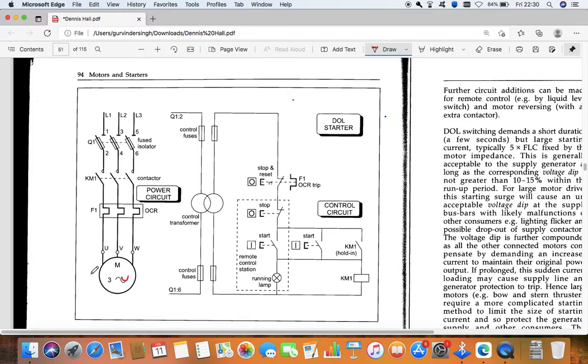Why do we require a starter? Let us consider this motor is a bigger one. When we start the motor, it will draw a very high current, so we need to reduce this current. Why is this motor drawing more current? Because in starting, the rotor is cutting 100% flux. When it is cutting the maximum flux, it draws more current and its power factor is also less. That's why it is drawing more current.